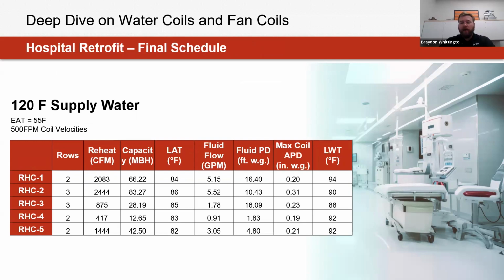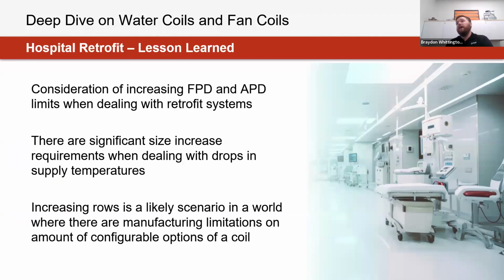Is it possible? Yes. One effective way, especially when looking at retrofits, as Heidi had mentioned in the chat, is actually going to be increasing the rows of coil. But one takeaway or reality of that, if you're dealing with retrofit projects, is that you're going to have to consider increasing the amount of water pressure drop that's going to be happening at that coil, and then also potentially tweaking what our threshold is going to be for the amount of air pressure drop coming from the coil as well.